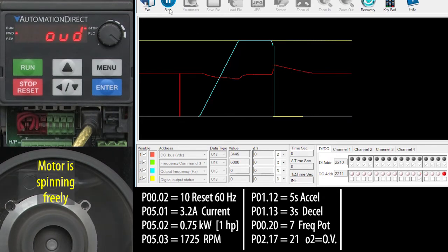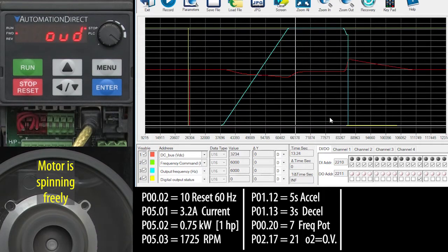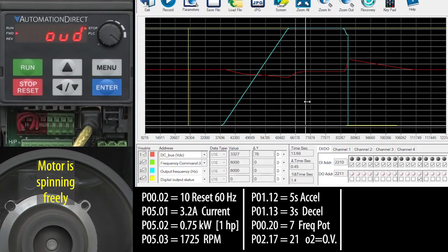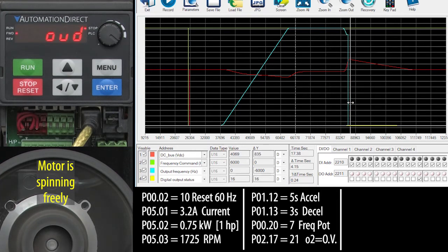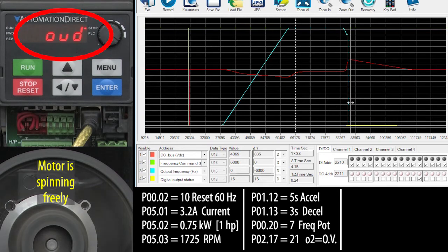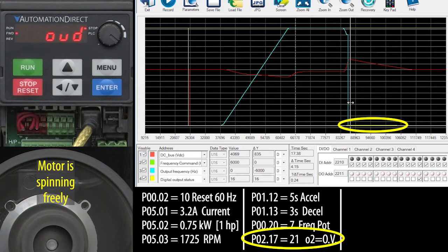I'll hit the drive stop button and let it run for a second. Let's stop the scope and zoom in on the results. When we hit stop, you can see the DC bus, which was around 335 volts, rose to over 400 volts. The drive saw that too and it gave up. It said I can't handle that and it dropped the output to zero and said good luck, you're on your own. You can also see when the drive hit the overvoltage condition on digital output 2.